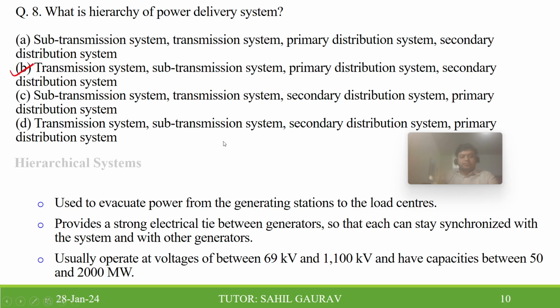Transmission system, sub-transmission system, then we have the primary distribution system and the secondary distribution system. I have noted the important points about this hierarchical system. First, the transmission system connects the generating power plants to the load centers and provides a strong electrical tie to generators so that they can be synchronized with the system. The operating voltage range is 69 kV to 1100 kV, with capacities between 50 and 2000 megawatt.